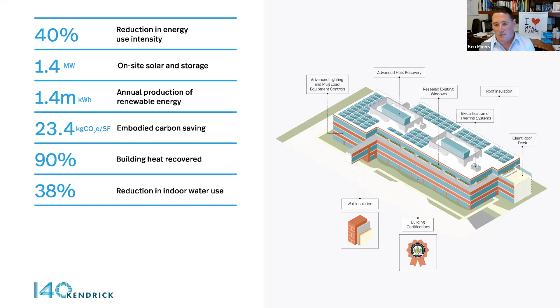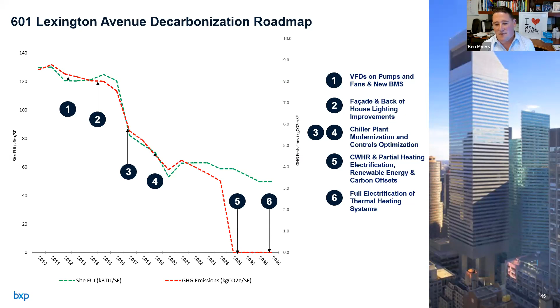At 601 Lexington Avenue, we're using water source heat pumps, unlike the last project's air source heat pumps, to recover heat from the central condenser loop. Through 2025, this building will be net zero carbon. It's a 1.7 million square foot office building in Manhattan, and it will cut its steam use 30% using heat pumps, having already cut steam use 60% by shifting from steam chillers to modern electric drive chillers.